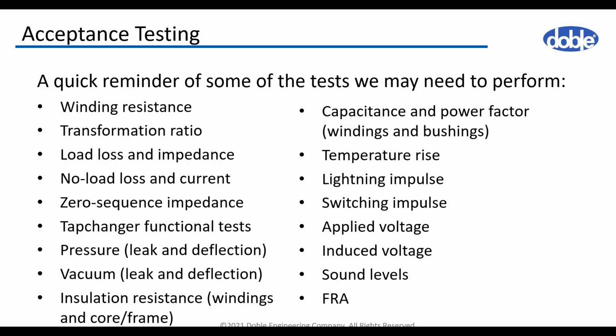This is a list of tests we need to perform during factory testing. It includes performance tests like no load loss and impedance, temperature rise test, sound level measurement. Also, it includes dielectric tests like lightning and switching impulse, applied voltage, induced voltage test, and so on.